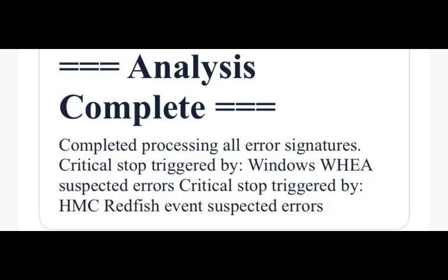So how did the framework nail this one down so quickly? They relied on the granularity of the error signatures they defined, specifically looking at the low-level cell logs from the power delivery subsystem. Once the pre-treatment cleaned those logs and the search and comparison flagged the signature, that RAG system kicked in. Exactly. The system automatically correlated the specific parameter that was failing in the log with the actual engineering specification for that device, which was stored in the vector database. The AI analysis instantly highlighted, hey, this device's behavior during that power spike is deviating significantly from how it's supposed to behave according to its own datasheet.